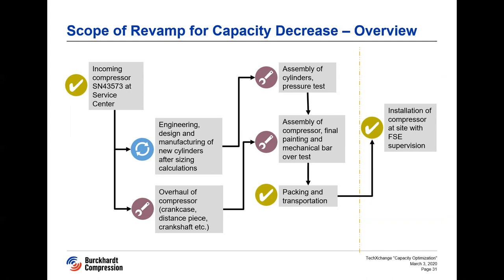Once the order was placed and the contract was signed, the client took care of dispatching the crankcase and the distance piece along with the internals to our service center. In the meantime, we started with the engineering, design, and manufacturing of the new cylinders. After the arrival of the crankcase and distance piece, they were thoroughly inspected and overhauled according to Burckhardt Compression standards. Once the new cylinders are manufactured and the crankcase and distance pieces are overhauled, they will be assembled together, painted, and a mechanical bar-over test will be carried out before being packed for transportation.